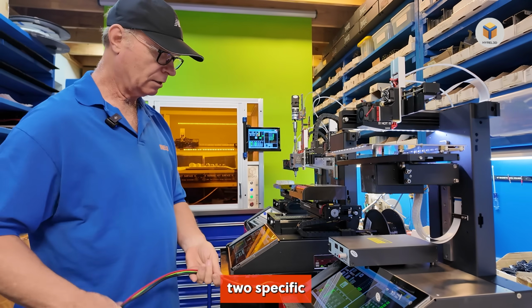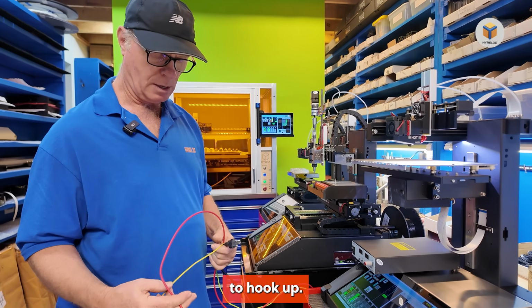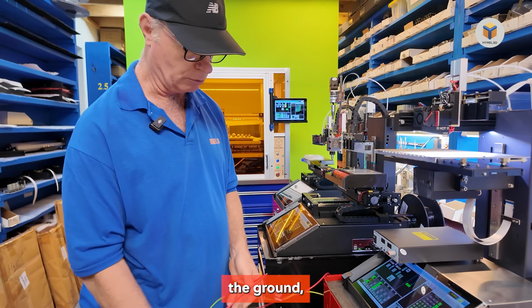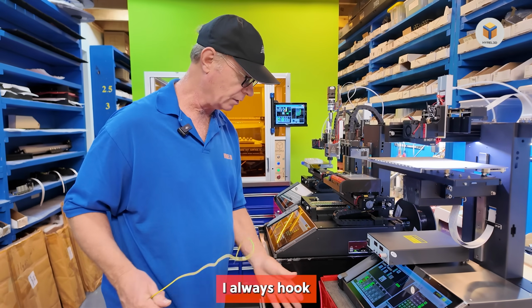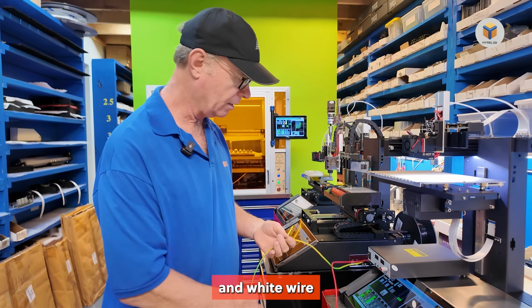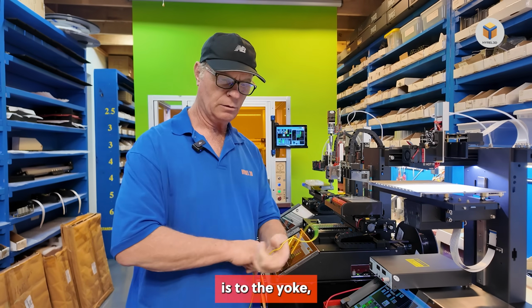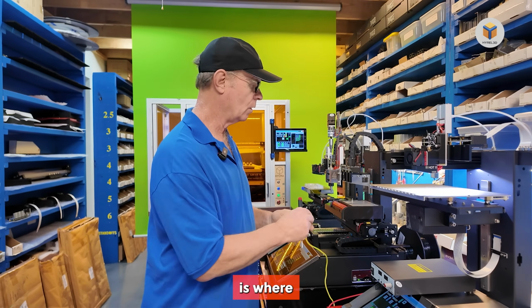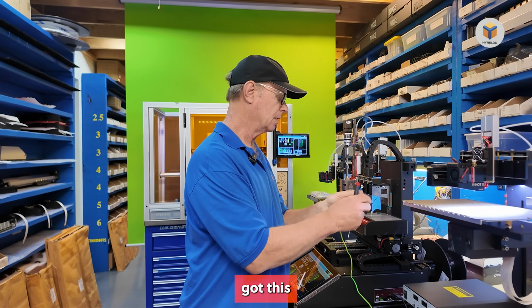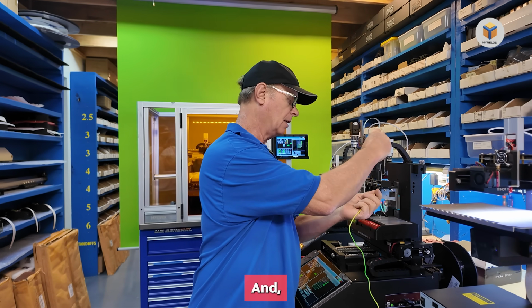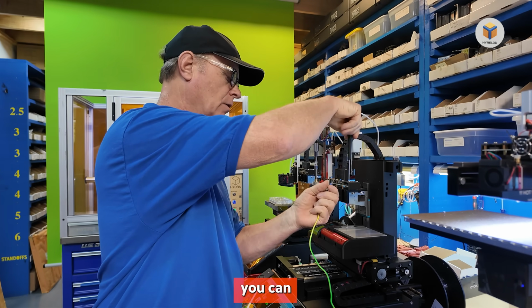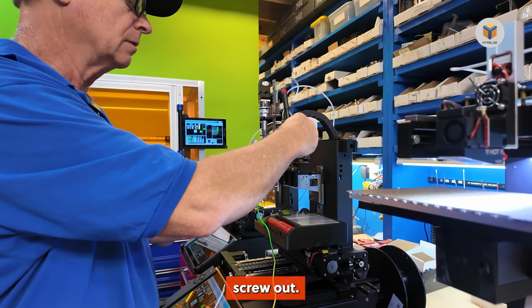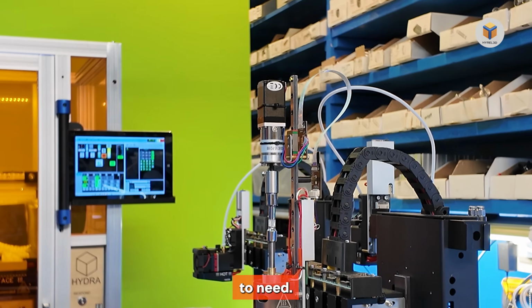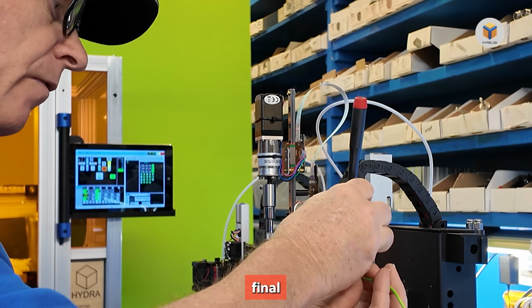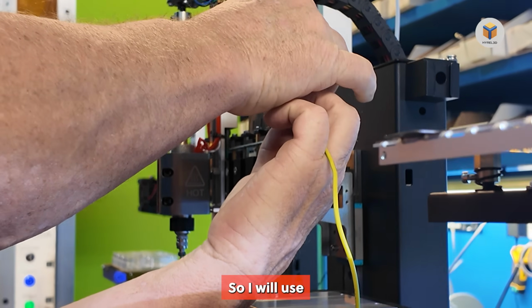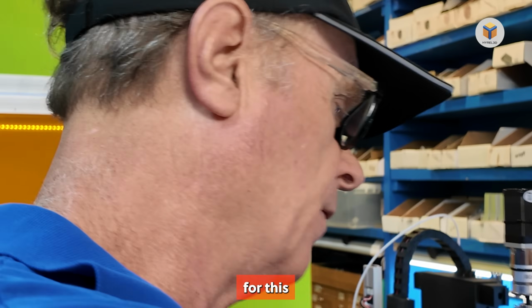And you have 2 specific cables you want to hook up. One of my favorite places to hook the ground, which is the first thing I always hook up, that would be the green and white wire, is to the yoke. Because this is where we want to make sure that we've got this solidly done. And you can take the front screw out. We will need a washer for the final installation, so I will use this over on its side for this moment.